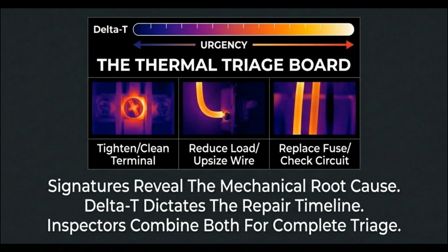The thermal triage board combines the fault's signature or mechanical root cause with the delta T to dictate the repair timeline. This combination provides a complete triage assessment.